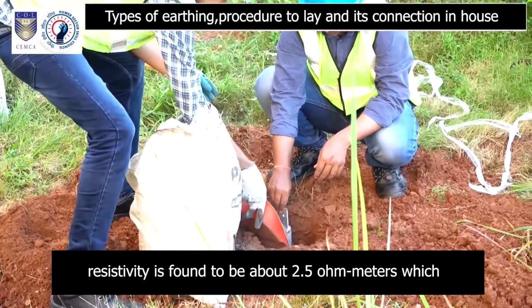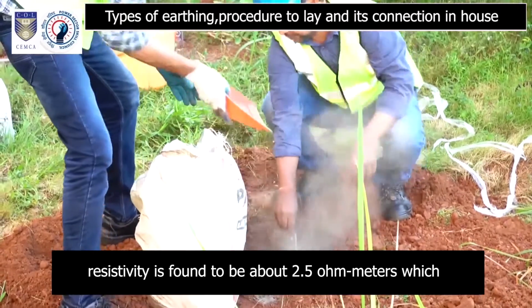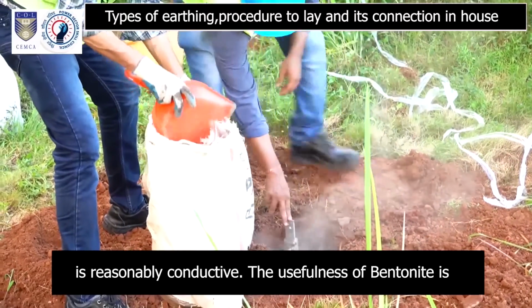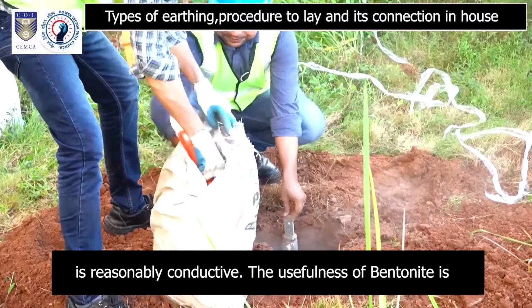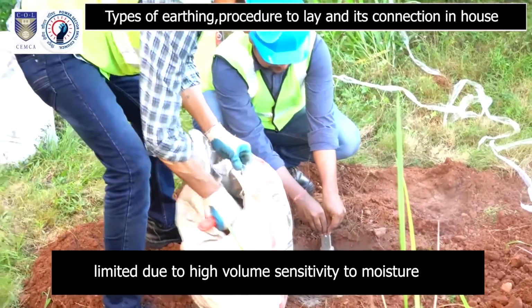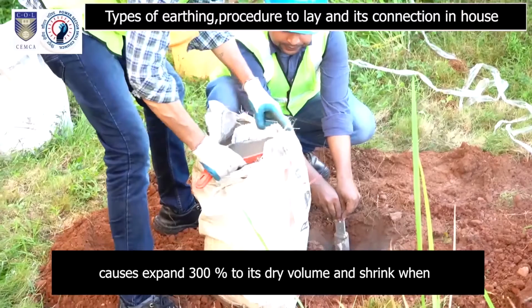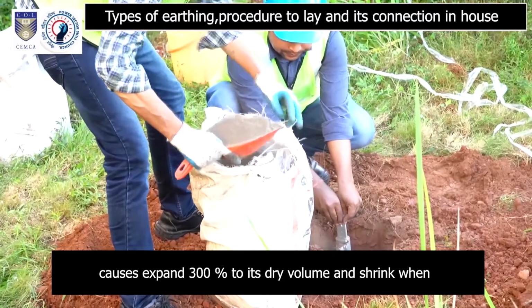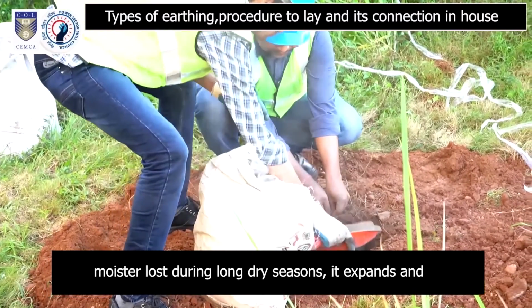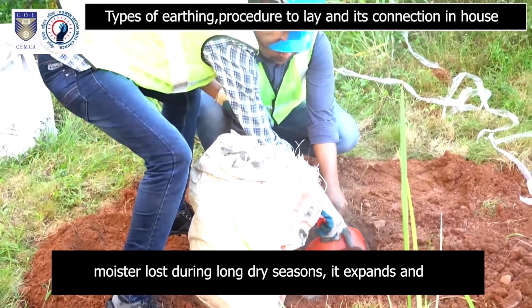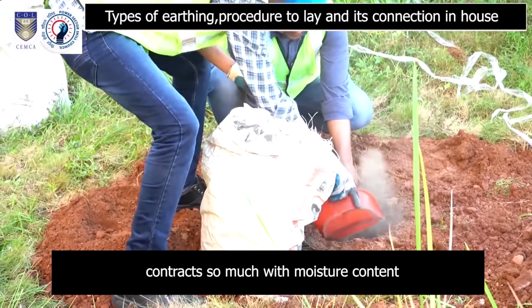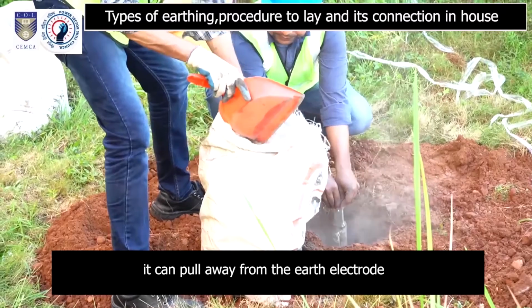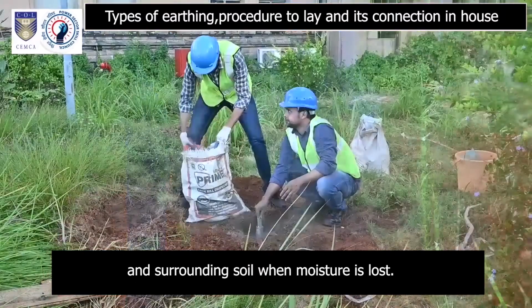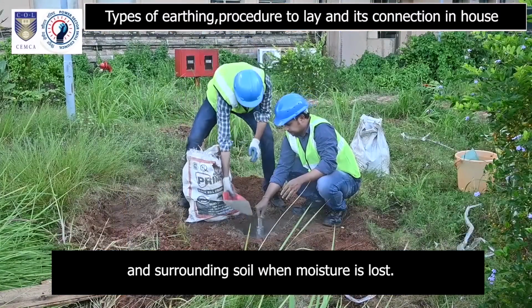Bentonite resistivity is found to be about 2.5 ohm meters, which is reasonably conductive. The usefulness of bentonite is limited due to high volume change. Sensitivity to moisture causes it to expand 300% of its dry volume and shrink when moisture is lost during long dry seasons. It expands and contracts so much with moisture content that it can pull away from the earth electrode and surrounding soil when moisture is lost.